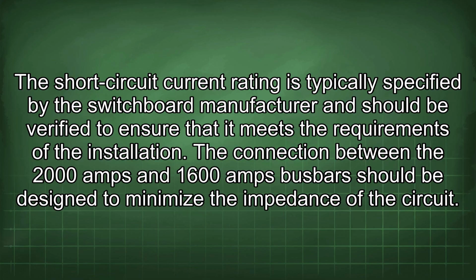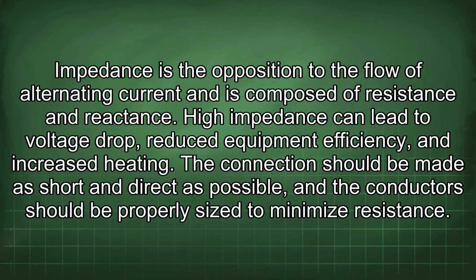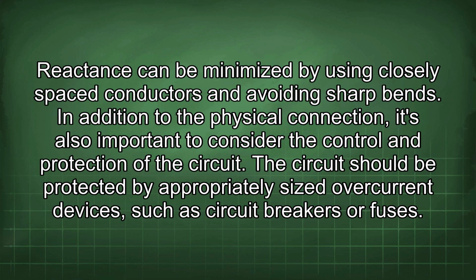The connection between the 2000 amps and 1600 amps busbar should be designed to minimize the impedance of the circuit. Impedance is the opposition to the flow of alternating current and is composed of resistance and reactance. High impedance can lead to voltage drop, reduced equipment efficiency, and increased heating. The connection should be made as short and direct as possible, and the conductors should be properly sized to minimize resistance. Reactance can be minimized by using closely spaced conductors and avoiding sharp bends.